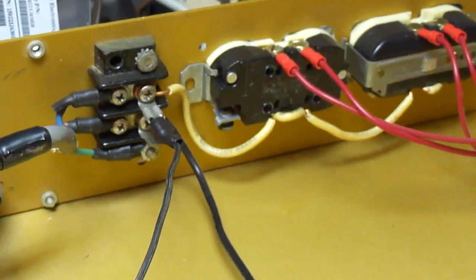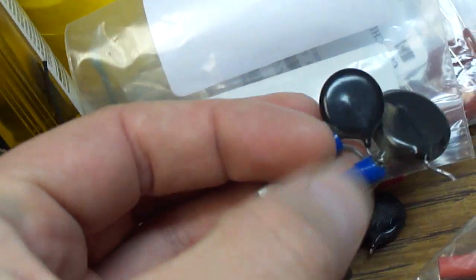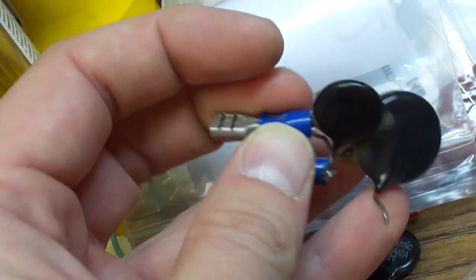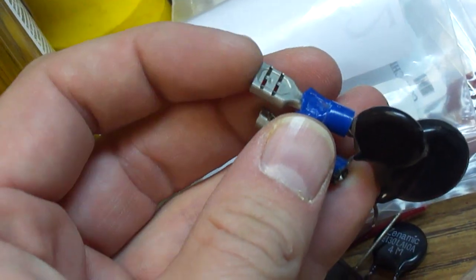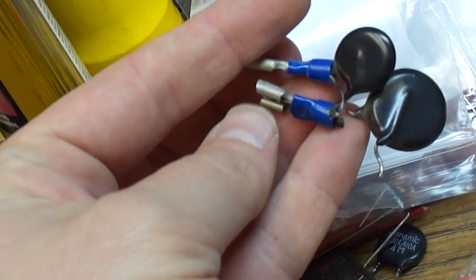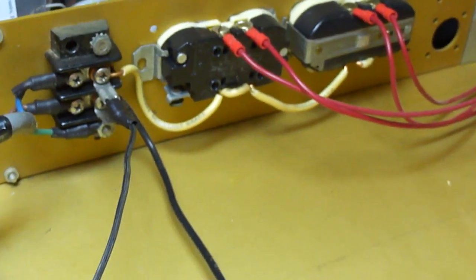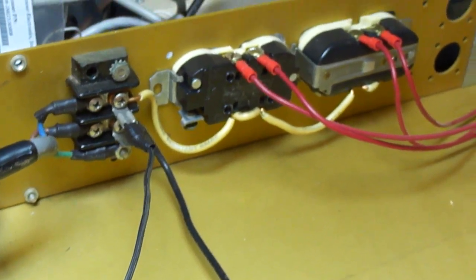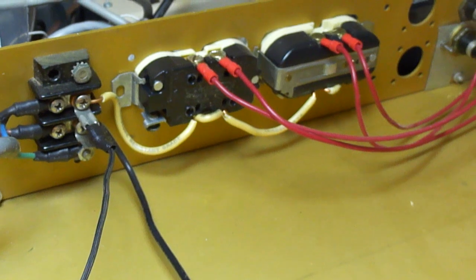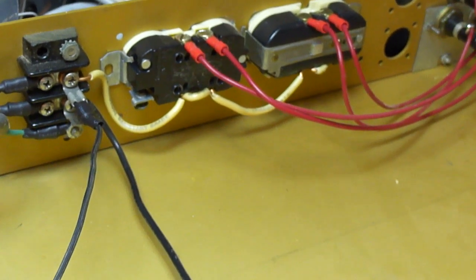But I really don't like to just use terminals like this that are crimped. Because like with these MOVs, the terminals can become loose from the connectors, or the terminal leads can come loose from the terminal lugs. And you can end up with oxidation between the wire and the terminals. So I like to always solder these even though they're designed to just be crimped. Soldering gives you a connection that's not going to oxidize.